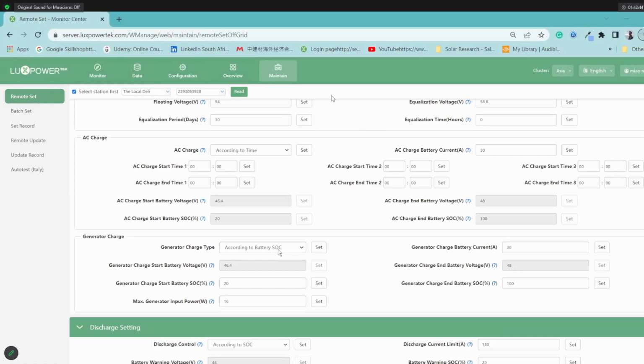Yes, that is a very, very good question. Okay, you can answer that. I will answer it, thank you. So in a parallel setup, when it comes to the panels, it's a little bit different than how you will set up batteries. You know, how you set up batteries in parallel, bus bar, and connect it to all of it. The panels, you can divide it across each inverter, it's fine. So you can have, let's say, one Luxpower inverter with 4 panels, the master. The slave has 12 panels, the other slave has 6 panels. It's perfectly fine, all on one. All in one, meaning all on one inverter, 6 panels times one inverter to charge. Oh no, that's fine, that's cool. But you don't have to connect to the second inverter. Yes, that's fine. Does that answer the question? I think it does, actually I had the answer.